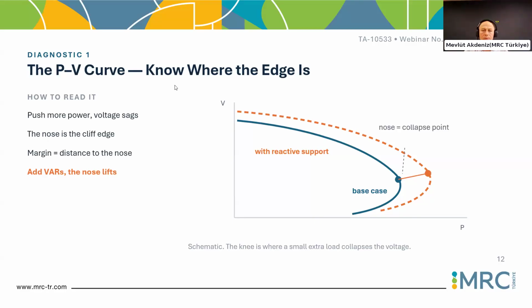Yeah, the PV curves are a very practical way of scanning the strength of the grid. Normally in a complicated or emerging grid, it may not be easy or practical in a short time to represent the grid model. That's another issue for planners or dispatchers, because to get a practical model in a valid condition, we should first take all the database, the data sheets, test results, and many forms of documentation, and transfer these data to our software. So it's not an easy task, to be honest, to make these dynamic or transient analyses very frequently in an automatic way.